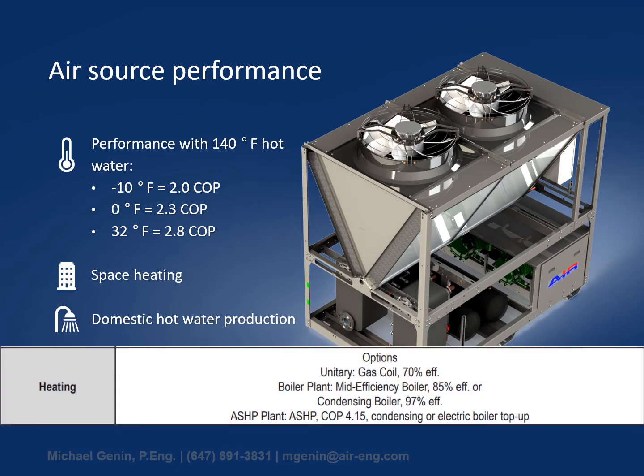And if you look at this snippet from the Toronto Green Standard, they're calling for an air source heat pump plant with a COP of 4.15. And as you can see, the efficiency gets better as the ambient increases, and this COP of 4 might be reasonable on a seasonal average, and that just means an average of the efficiency throughout the season, weighted by how many hours are spent at each temperature. So air source heat pumps are really becoming more popular. The COP you can expect is about 4.